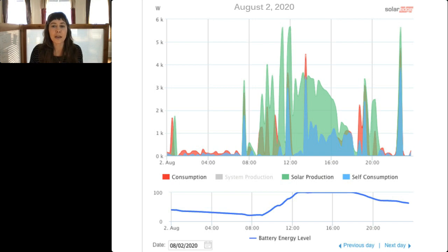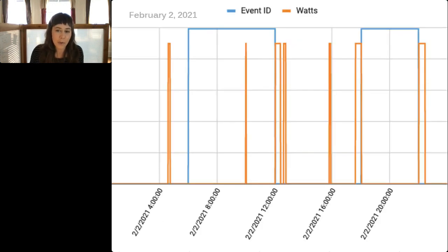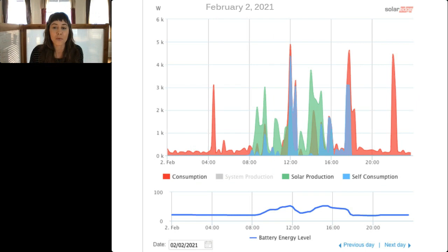Here you can see the same thing. Obviously, there are some minimum requirements that water heater is going to need for maintaining water heat, so there is a small charge right here. But when we extended the window, even in the middle of winter, we can see mostly that snapback for the water heat was in periods outside of the shed command. And again, here we can see how that aligns with solar energy even in winter.